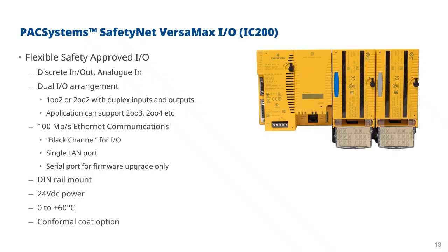Now with this one, we have the safety bus interface there with its Ethernet. It's got a single LAN port which supports 100 megabit Ethernet, again using that black channel for I/O communications. So that would be connected to the controllers. In a small application, you could potentially use a single Ethernet cable directly to the controllers. But in most applications, there would be the requirement for some sort of external switches. But because we're using black channel, they don't necessarily have to be Emerson switches. It can be any switch.